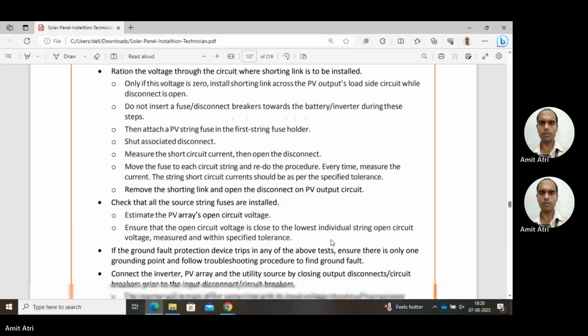Okay, now we have connected. Shut the associated disconnect. So the short circuit current that is flowing, now just measure it. The ISC value that is flowing, we have to measure it. Then open the disconnect. Again, break the connection. Then move the fuse to each circuit string and redo the procedure. Means every circuit string we have to check. So every time measure the current.